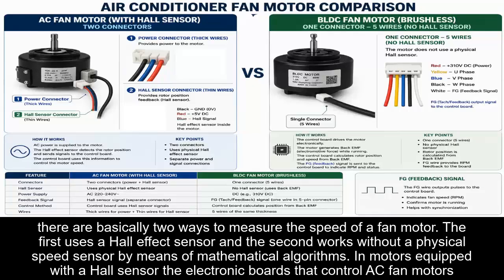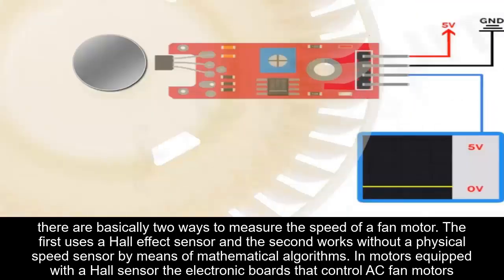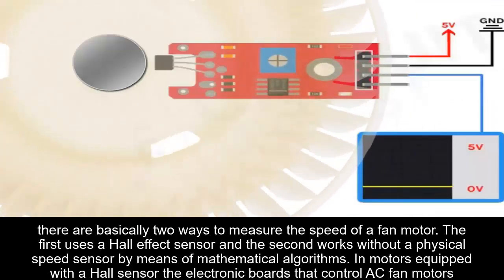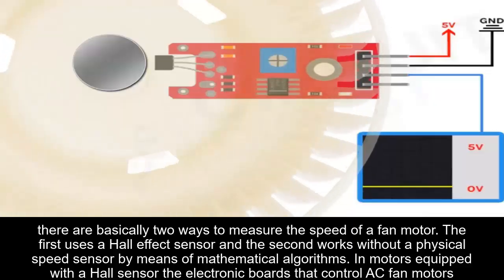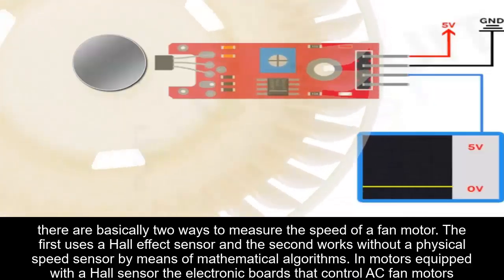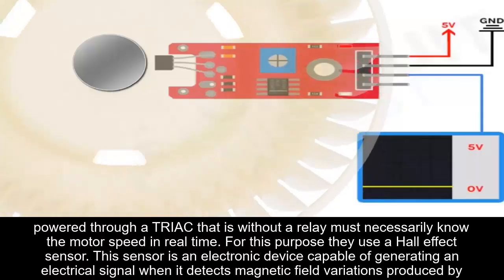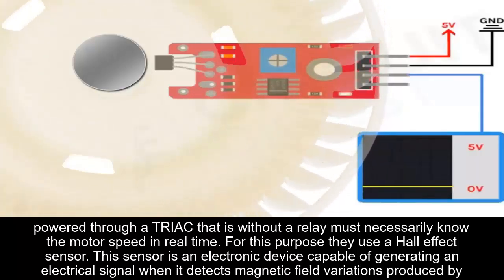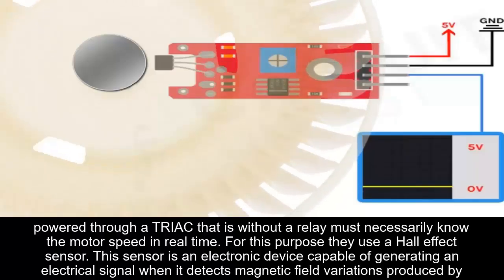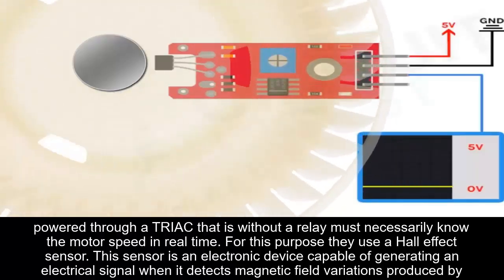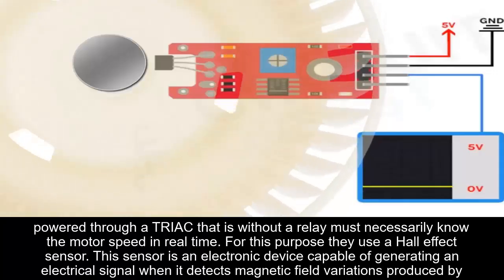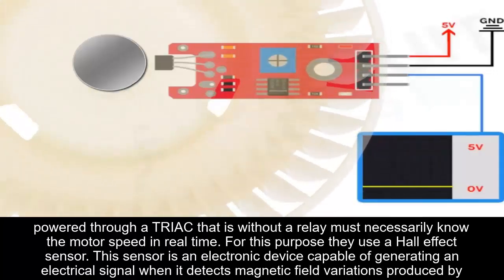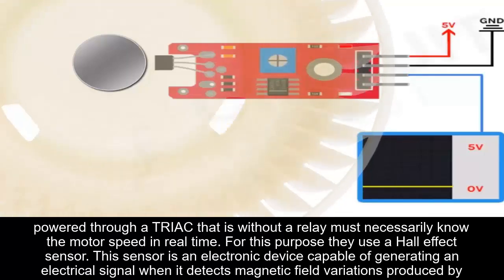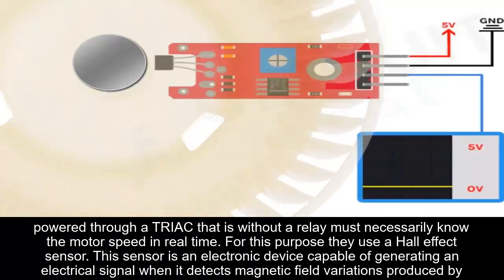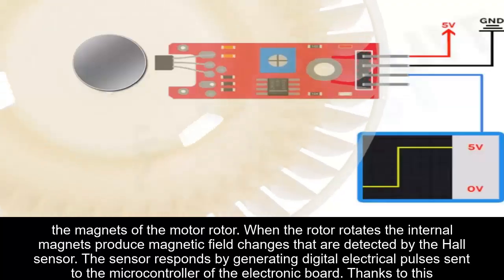The first uses a Hall effect sensor, and the second works without a physical speed sensor by means of mathematical algorithms. In motors equipped with a Hall sensor, the electronic boards that control AC fan motors powered through a triac, that is, without a relay, must necessarily know the motor speed in real time. For this purpose, they use a Hall effect sensor. This sensor is an electronic device capable of generating an electrical signal when it detects magnetic field variations produced by the magnets of the motor rotor.